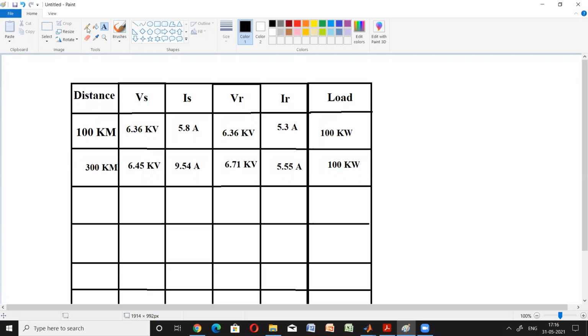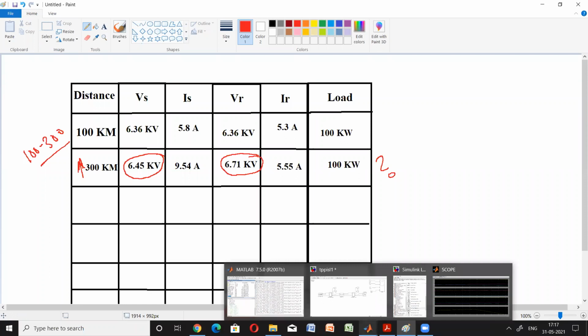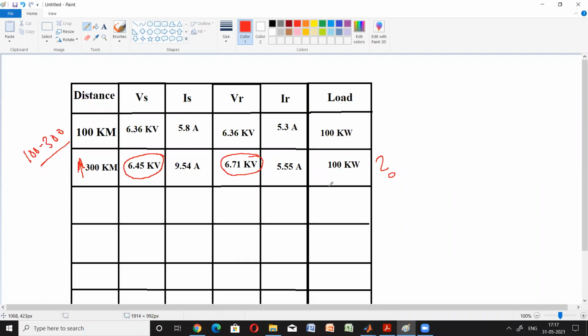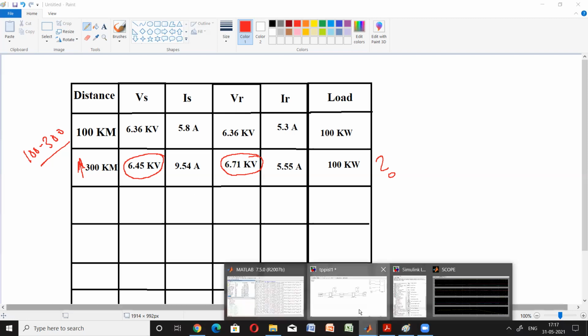Now we are getting something very interesting here. What we find is, if we increase the distance from 100 to 300, one interesting thing happens: the sending end voltage is 6.45 kV, but the receiving end becomes 6.71 kV. Why? You can see here the sending end voltage in the previous case is around the same, but now we are not changing the load, only increasing the distance. And when we increase the distance, the receiving end voltage becomes quite high, more than the sending end voltage. Why did this happen here?